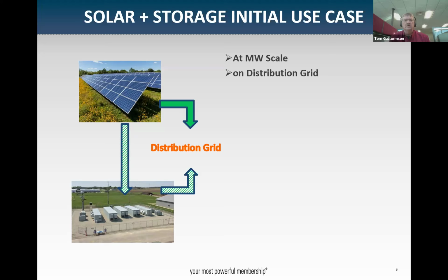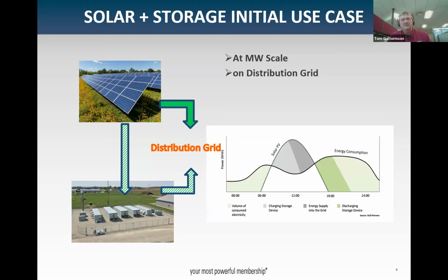The administrative rules were that if we used the storage for demand response, charging the batteries and discharging them at peak to reduce consumption from our substation meters, our wholesale supplier required all that energy to be charged into the battery from the solar system. So we devised a way to do that legally that met everyone's administrative requirements. That's what the batteries are for. Basically it's shifting - the batteries are not a generator, they're a garage. We're purchasing the electrons from the solar system, storing them in the garage, and taking them out when we need them to reduce demand at system peak.